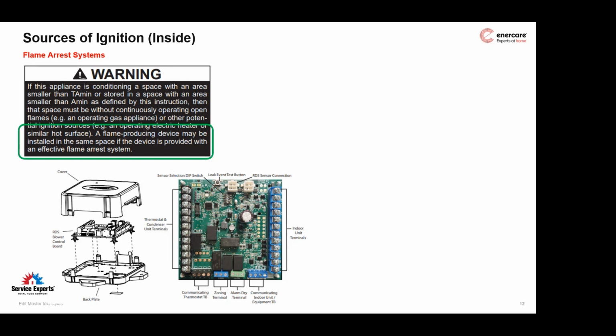So for instance, on screen right now, Lennox has this external RDS board that can be put on after the fact. For instance, you put a new A2L heat pump or air conditioner on an old legacy system that they're not replacing. So there was another furnace there, installed 5 years ago, nothing wrong with it, but it just so happens the homeowner's changing their air conditioner or heat pump. This board and a sensor can be put on and tied in as a pass through, basically the thermostat down through the thermostat wire. This basically sits in the middle between the thermostat and the furnace. It just acts as a pass through, and its only job is, if there's ever a leak, it stops the heating or cooling from functioning. We'll get into it a little deeper.